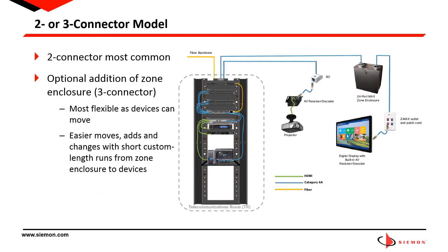The most common configuration for structured cabling systems is a two-connector model, where there is a patch panel in the telecommunications room and an outlet adjacent to the device with a patch cord at each end. However, to allow greater flexibility and to simplify moves, adds, and changes, a zone enclosure can be added in which the permanent cabling is installed between the telecommunications room and the zone enclosure, and then changes are limited to a much smaller and less disruptive scope between the zone enclosure and device outlets only. Note that in addition to the cable itself, all connectivity such as outlets, housings, and enclosures must be plenum rated if located within an air handling space.